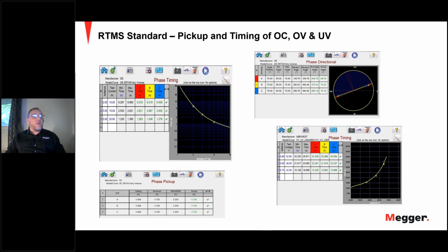The time overcurrent screen includes the options to do electromechanical relays, pickup test, and instantaneous pickup test. And the TOC screen allows the user to select up to 20 elements, and the curve selection has either ANSI, IEC, IEEE standard time curves, as well as relay manufacturer specific curves.